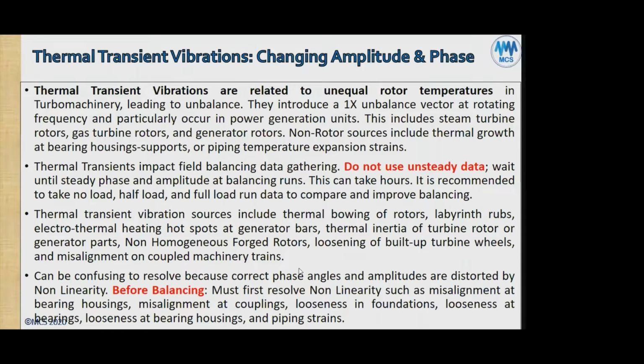on this slide, we discuss thermal transient vibrations and where they came from. Thermal transient vibrations are related to unequal rotor temperatures in turbomachinery, leading to unbalance. They introduce a 1x, a 1 times running speed, unbalance vector at rotating frequency, and occur mostly in power generation units. This includes steam turbine rotors, gas turbine rotors, generator rotors. Other than the rotors, we have non-rotor sources, which include thermal growth at bearing housings and supports, or piping vibration expansion strains. These thermal transients impact field balancing and data gathering. So the thermal transient vibrations, as we said, are usually mostly related to rotors. However, they can also be, of course, caused by bearing housing support growth or piping temperature expansion and strains.